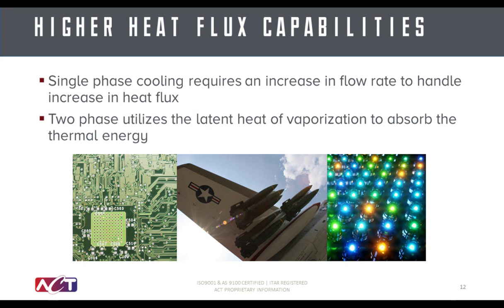High heat flux components don't necessarily need to be cooled with a two-phase cooling approach. It can be done with single-phase cooling. However, the challenge is that a large amount of flow rate is required. This often means sending high velocity fluid through the cooling channels, as opposed to a two-phase system, which would be a much lower flow rate.